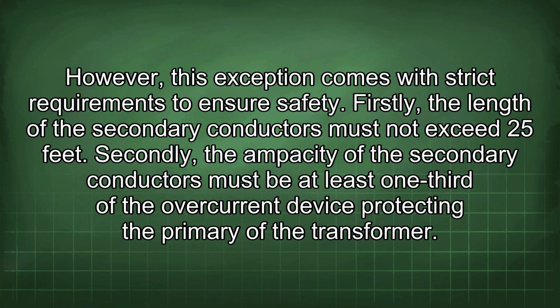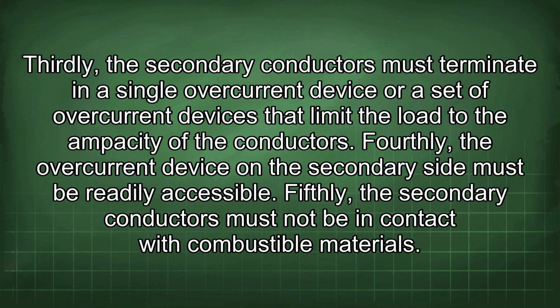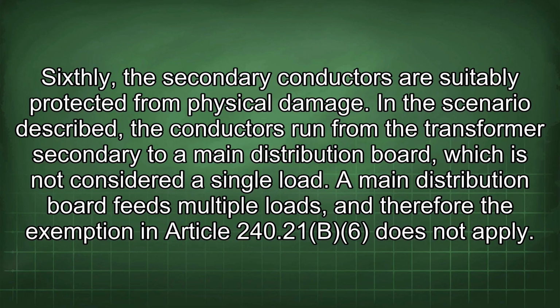Firstly, the length of the secondary conductors must not exceed 25 feet. Secondly, the ampacity of the secondary conductors must be at least 1/3 of the overcurrent device protecting the primary of the transformer. Thirdly, the secondary conductors must terminate in a single overcurrent device or a set of overcurrent devices that limit the load to the ampacity of the conductors. Fourthly, the overcurrent device on the secondary side must be readily accessible. Fifthly, the secondary conductors must not be in contact with combustible materials. Sixthly, the secondary conductors are suitably protected from physical damage.